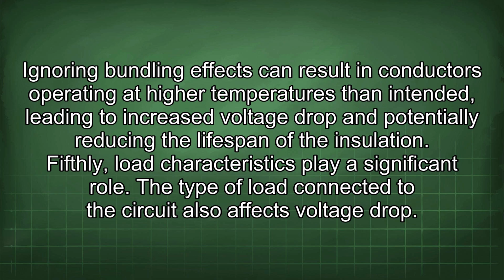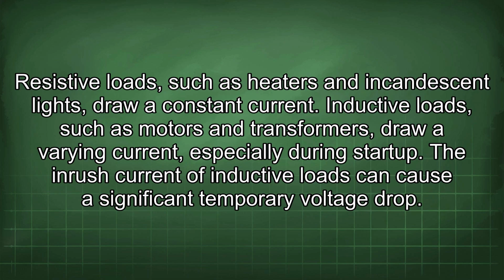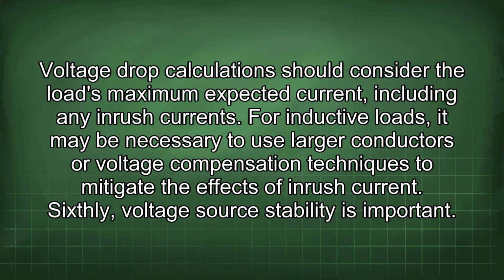Fifthly, load characteristics play a significant role. The type of load connected to the circuits also affects voltage drop. Resistive loads, such as heaters and incandescent lights, draw a constant current. Inductive loads, such as motors and transformers, draw a varying current, especially during startup. The inrush current of inductive loads can cause a significant temporary voltage drop. Voltage drop calculations should consider the load's maximum expected current, including any inrush currents. For inductive loads, it may be necessary to use larger conductors or voltage compensation techniques to mitigate the effects of inrush current.